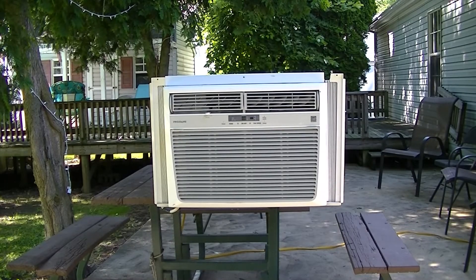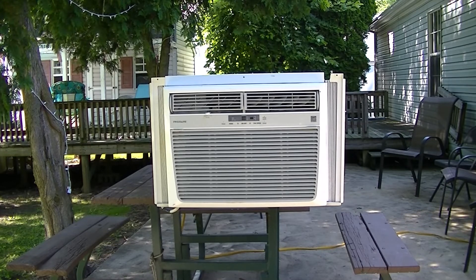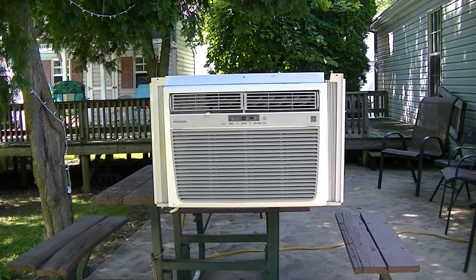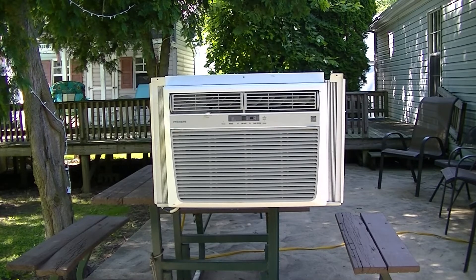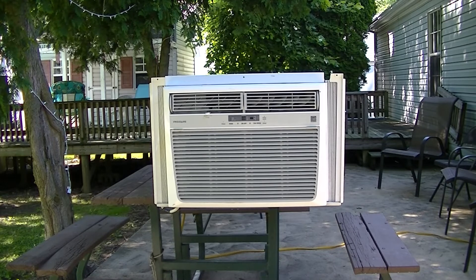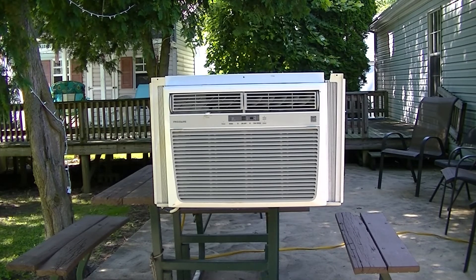So this unit has passed the test. Ideally you want a 20-degree difference — this one was fluctuating a little bit, but I might have been hitting some of the plastics in there. If it's over 20 degrees, it's overcharged; if it's less than 20 degrees, you need a charge. I'd like to thank everyone for watching — any questions or comments, leave them down below.